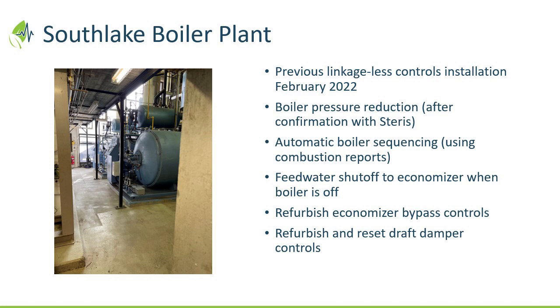Paul, what kind of issues does that make? Because the higher the chimney, presumably the more it's trying to pull the air through the boilers and costing us energy, right? Yeah, I mean, a stack that big, especially in the winter, will create draft that'll pull your hat off, right? Like, there's a significant delta between winter and summer in terms of how draft is going to play on that. And we've seen over the last few days with the weather we've had, you're still getting fairly cool mornings, sometimes with some upset weather conditions in the middle of summer, and then it's 30 degrees out in the afternoon. So, like, across a stack that big, that is a significant change in draft. And that will have a significant impact on combustion, if not controlled.